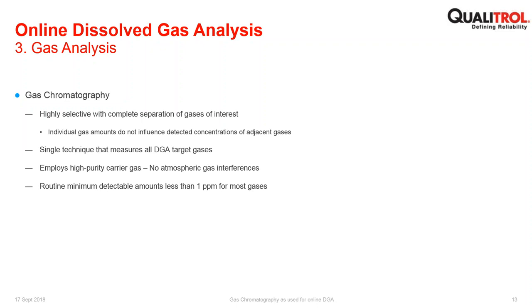And that is something that you see with infrared spectroscopy, and often with solid-state sensors, that they have some type of cross-sensitivity or interference from one gas to the next adjacent gas. That's avoided completely with dissolved gas analysis by gas chromatography. And that is the key to why gas chromatography is used in all of the laboratories. Globally, all laboratories that do dissolved gas analysis will use gas chromatography for this specific reason. And because you get complete separation, you can have complete and demonstrable confidence in the accuracy of the measurement. You have isolated the gas and you're measuring the gas in an isolated form.